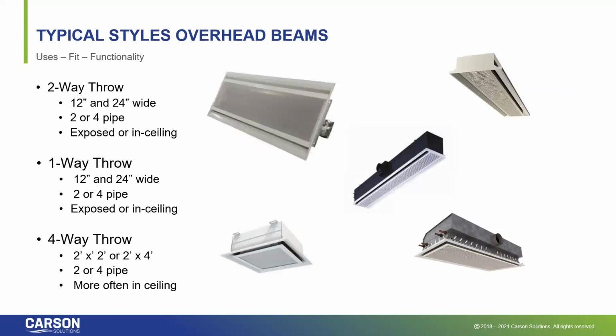Along those lines of different types of chill beams, in the upper portion of the slide is a two-way throw chill beam, throwing supply air out in two directions, and those are suitable for 2-pipe or 4-pipe applications. You can get those in 1 foot and 2 foot wide variations. In the middle of the screen is a one-way throw, which only throws in one direction, again suitable for 2-pipe or 4-pipe, exposed mounting or in-ceiling mounting, also in 1 foot and 2 foot width dimensions. And then there are also 4-way throw chill beams as an option, and those throw, as their name implies, both east and west, as well as north and south, depending upon the application and suitability.